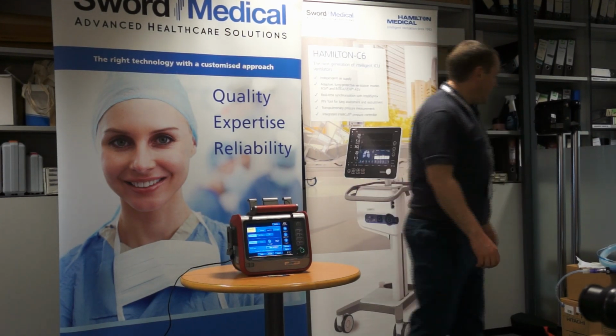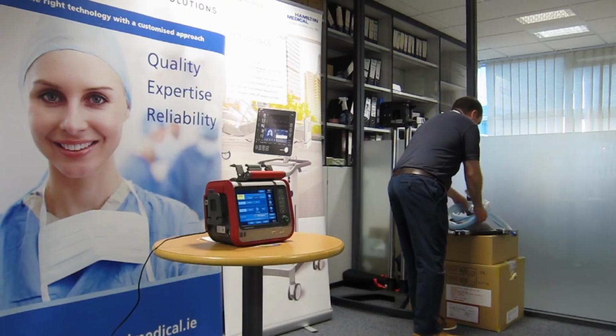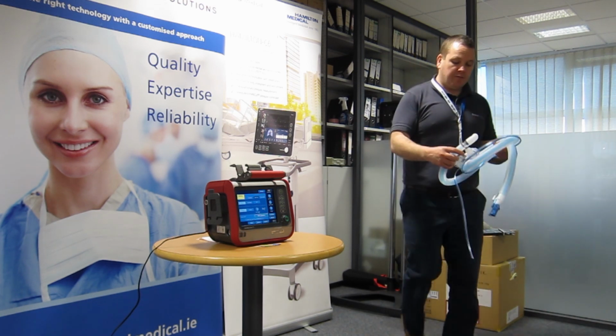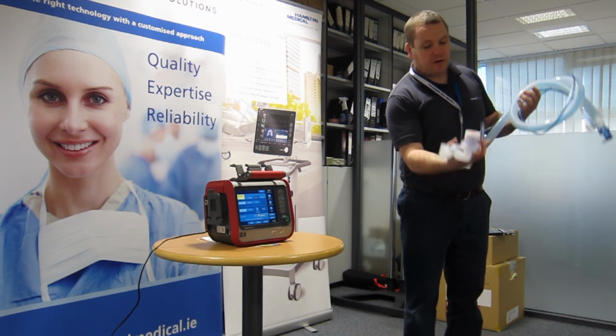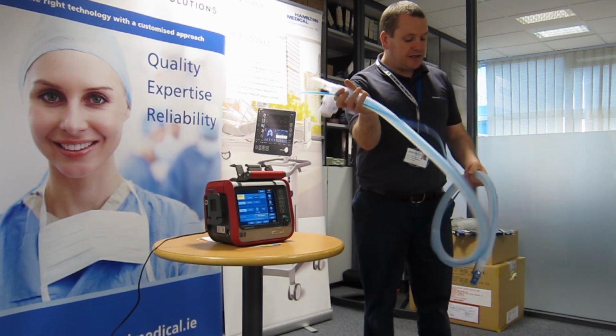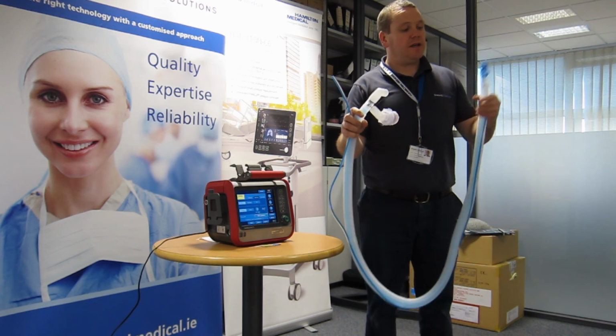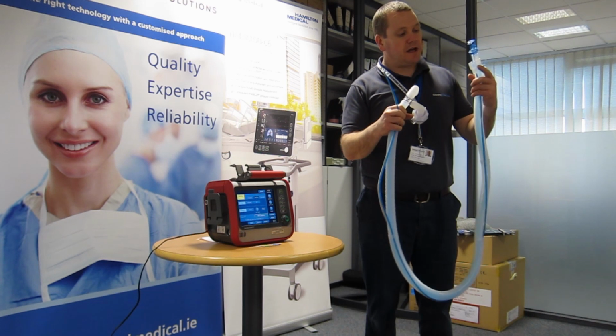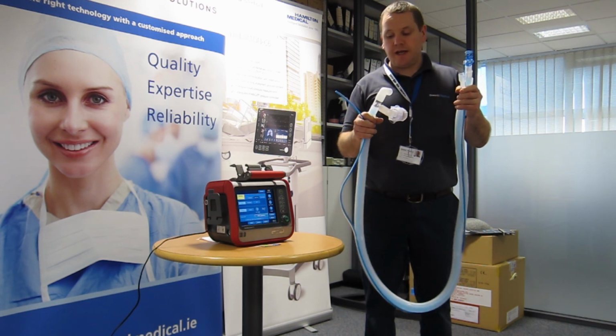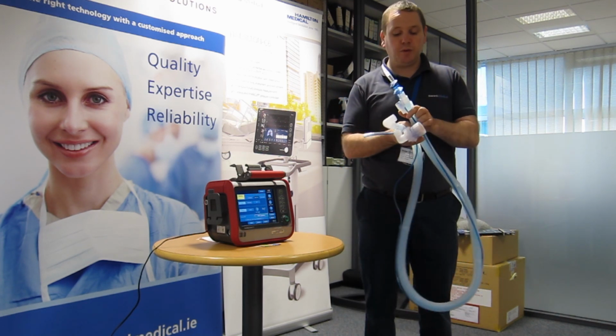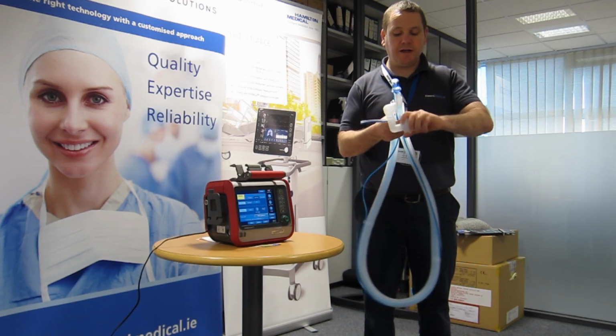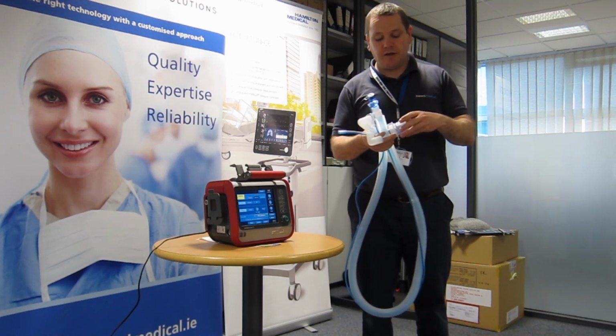So here then is my circuit. And as you can see, I have my expiratory valve and flow sensor tubing on this end of the circuit, and on this end of the circuit I have my blue flow sensor with my sizing adapter that we're going to use to calibrate the flow sensor. So I'm going to plug on the circuit. I always take off my expiratory valve when I'm plugging it on. Much easier to plug on.